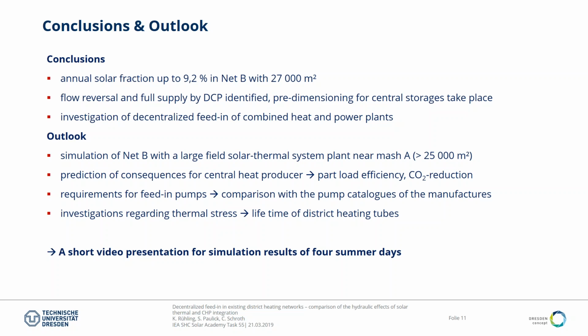What's our outlook? We want to run more simulations with network B, or with a standalone solar thermal plant in the range of 25 to 50,000 square meters. We want to predict the consequences for central producers concerning part-load efficiency and CO2 emissions. We want to identify the requirements for the pumps and investigate thermal stress, and the lifetime of the district heating pipes.